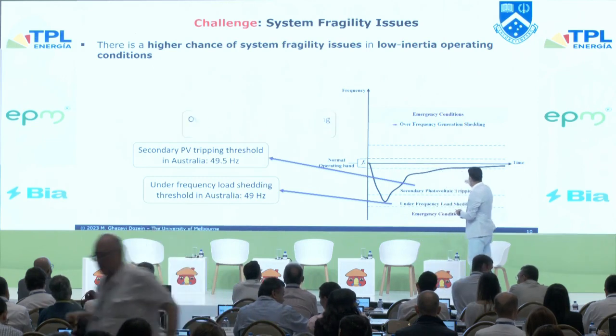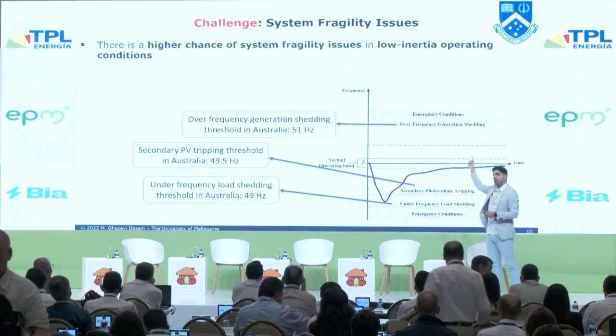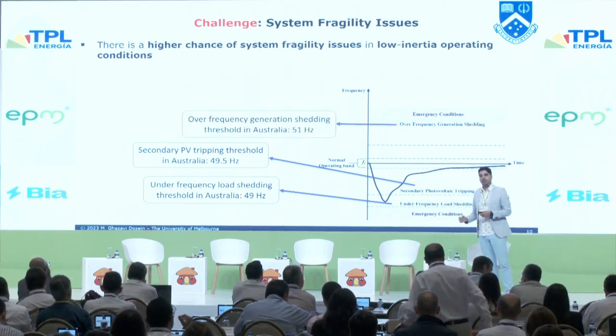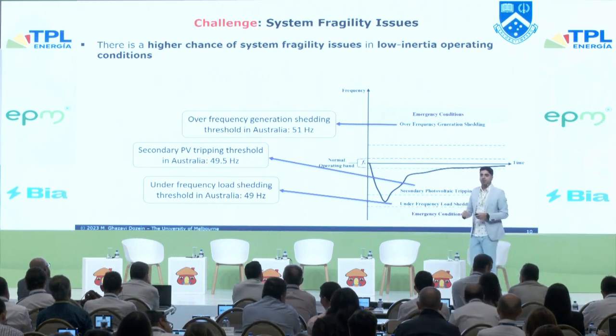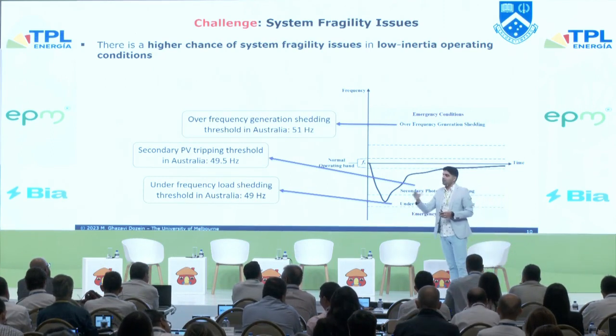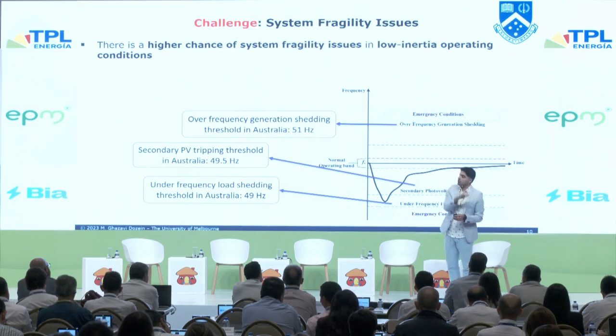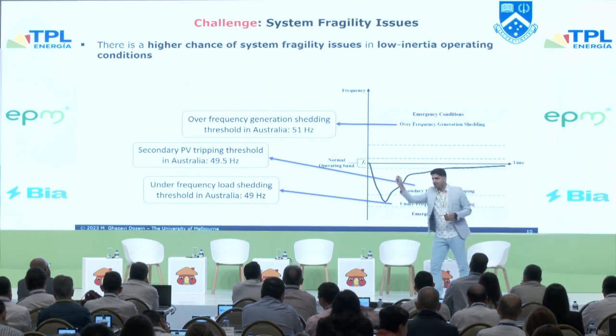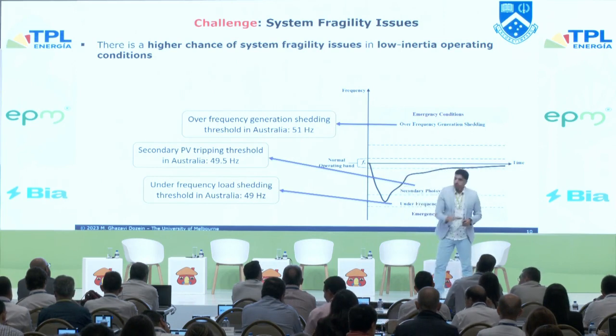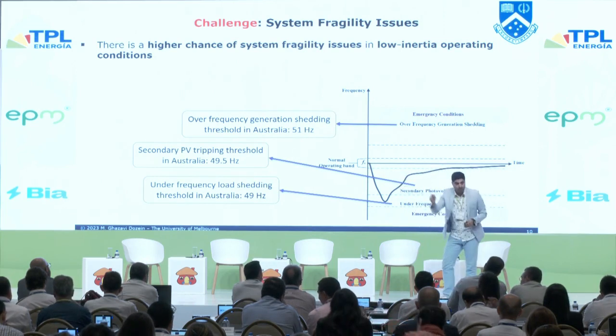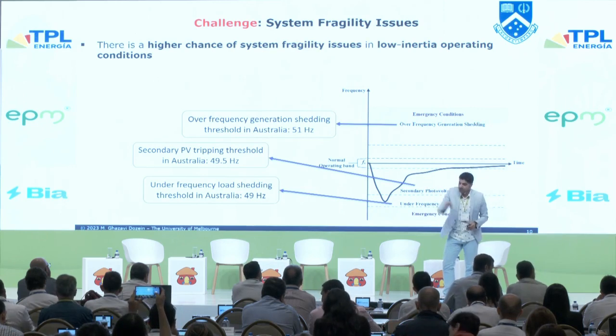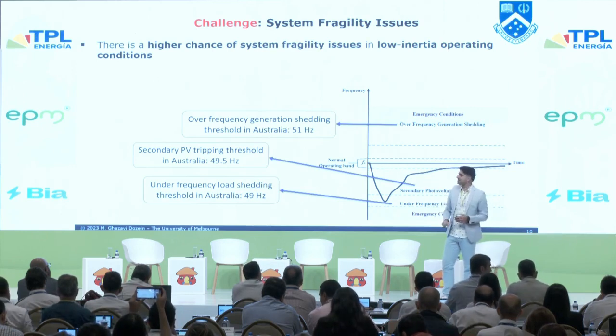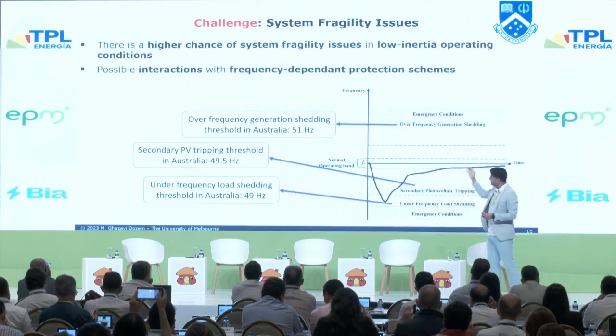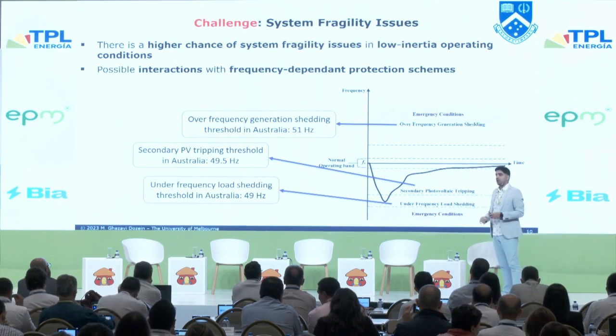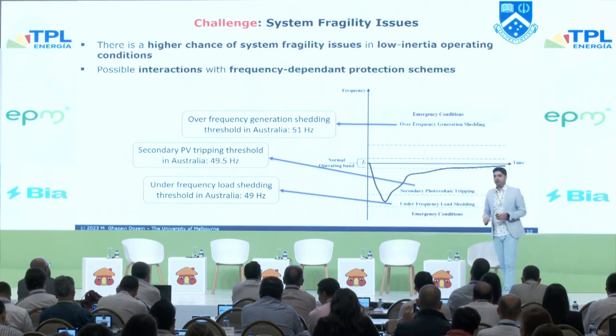Or in the case of an over-frequency condition, if frequency goes above 51 hertz, some generation would trip to mitigate the active power mismatch caused by a contingency. So think of this: one event can result in a chain of events. A couple of trippings may happen, a lot of disconnections may occur in the system. So there is a possible interaction between protection operation and frequency stability.